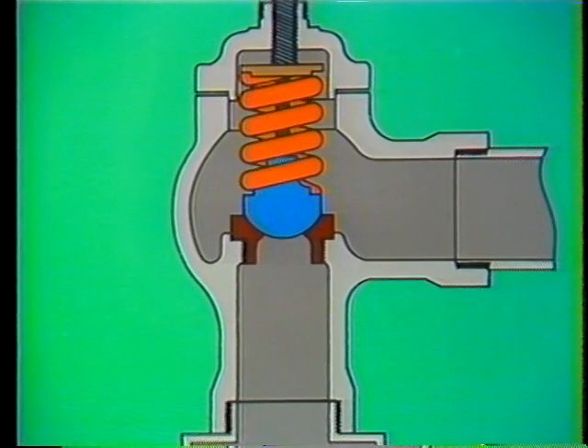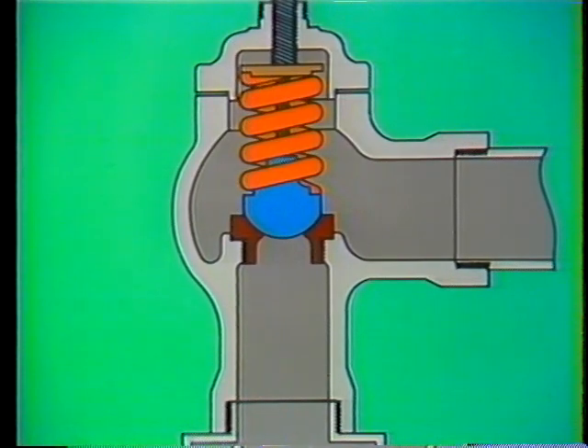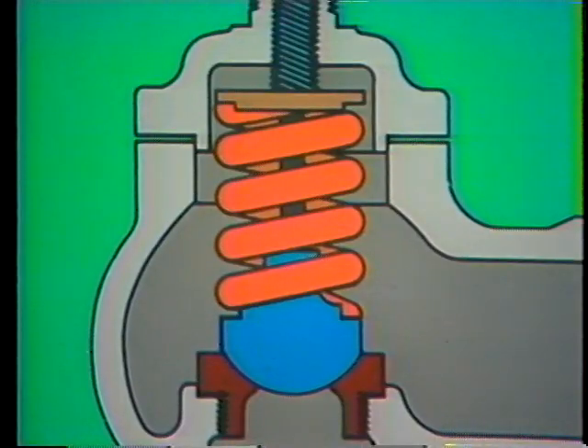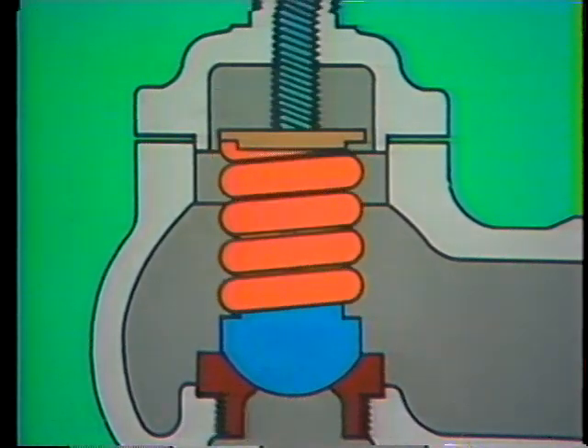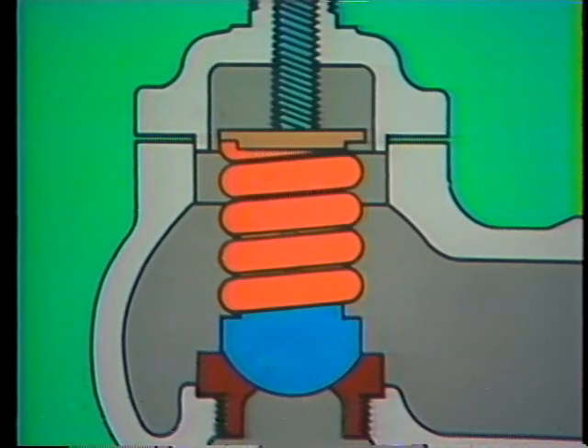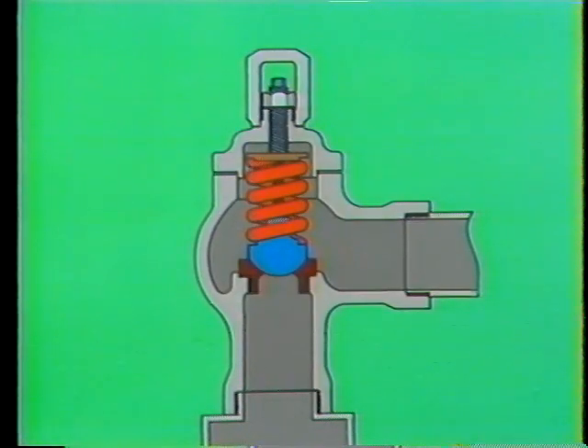You can see how important proper spring tension is to the function of a relief valve. But like any other component, springs wear after extended service, losing some of their stiffness. This changes the opening and closing point of the valve. To correct this, the spring adjusting screw can be tightened, which increases tension on the disk and raises the opening pressure of the valve. Loosening the adjusting screw has the opposite effect — it reduces the amount of tension on the disk, allowing the valve to open at a lower pressure. Remember, though, that each relief valve is designed to handle a certain range of pressures, so each can only be adjusted so much. Before making any adjustment to any relief valve, consult the manufacturer's instruction manual. Know exactly what you're doing before you do it.